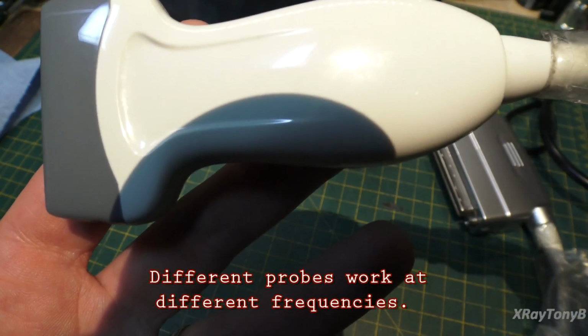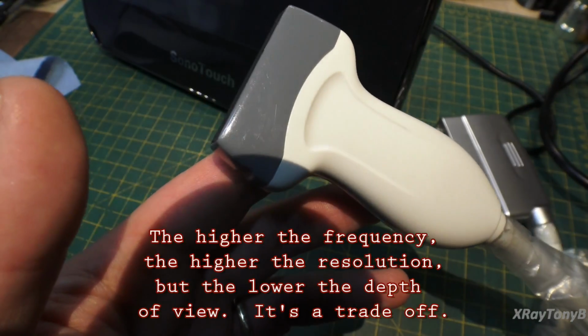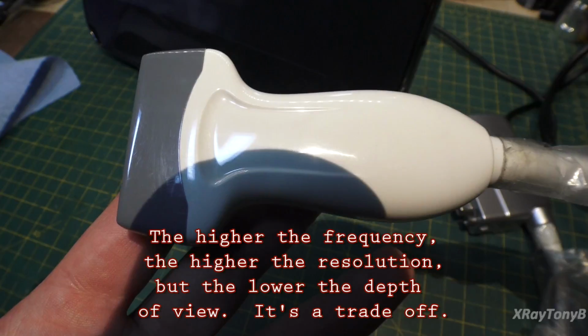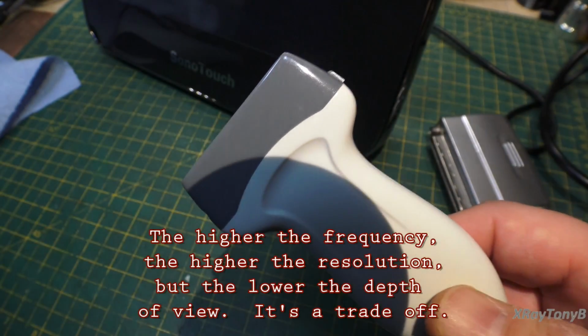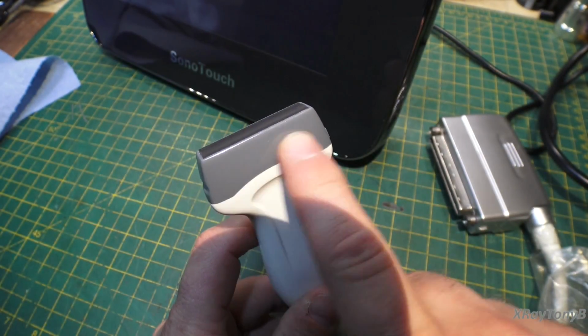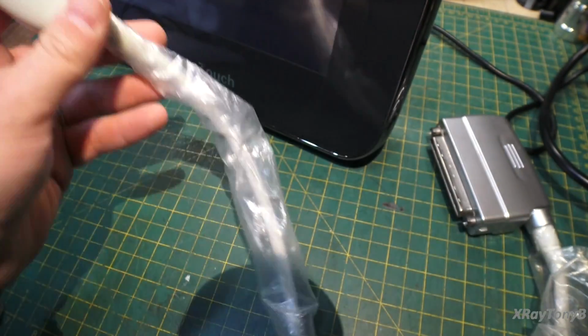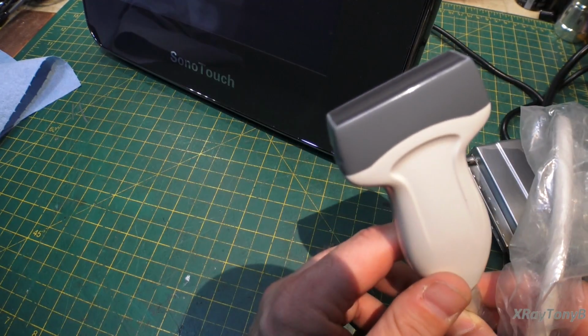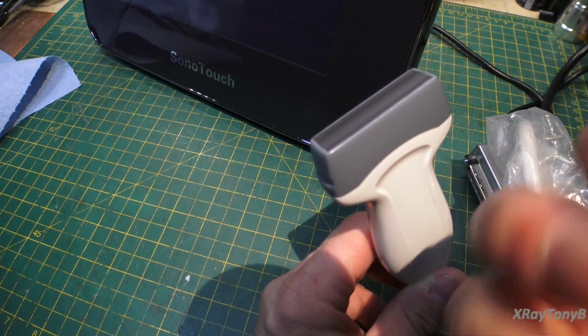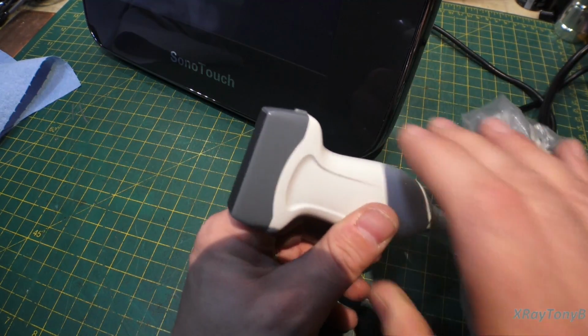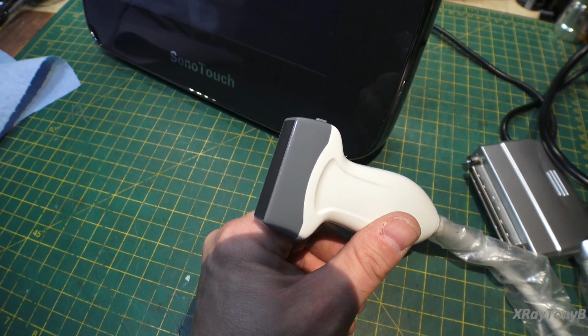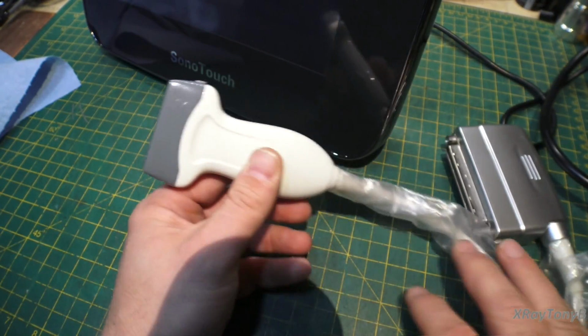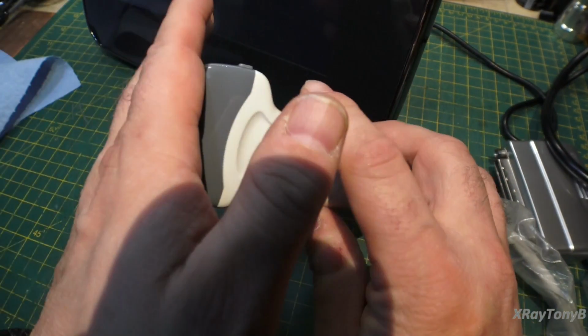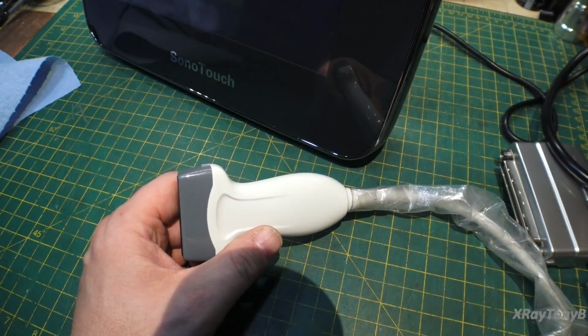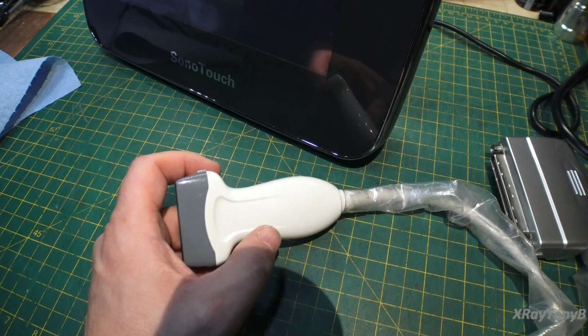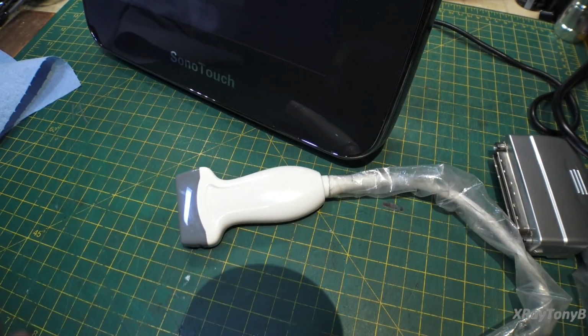So 7.5 megahertz, any of you ham radio operators can know what band that's in, but that's higher than the AM radio band, but lower than FM radio. But it is radio frequency. However, this is not an electromagnetic wave that comes out of here. Okay, so it's not even RF per se, even though it's in the frequency range of what we call radio wave or RF. But it's actually sound pressure. And because of that, ultrasound needs to have a medium to propagate through. Now, what do I mean by that? Well, what that means is in order for this to work, it has to have some medium to vibrate through, to propagate through. Whereas radio waves or electromagnetic waves can travel even in a vacuum. So that's why radio waves can travel through space.